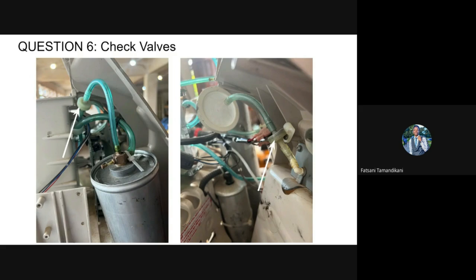A colleague shares a field experience: while assessing a concentrator in the wards, they found it reading 21% oxygen purity. Upon opening it, they discovered water had reached the sieve beds — the zeolite was wet and the filters were damaged. It is advised to add check valves to prevent both backflow of oxygen into the sieve beds and backflow of water into the concentrator.